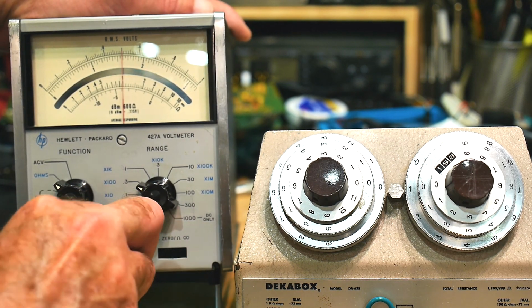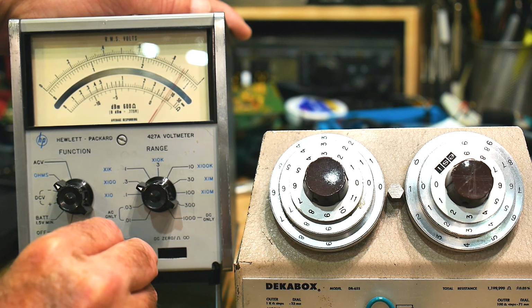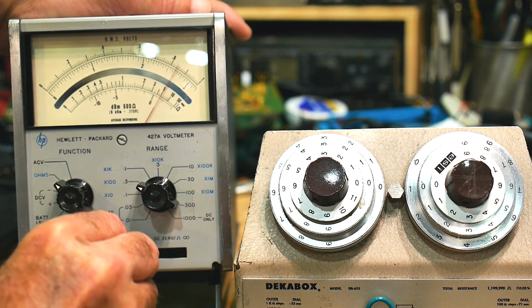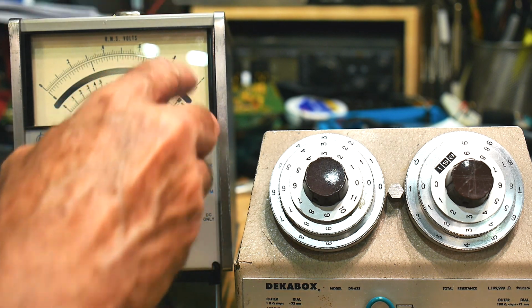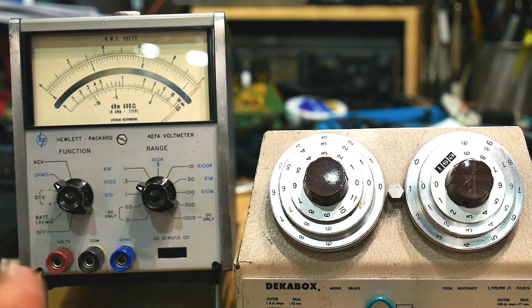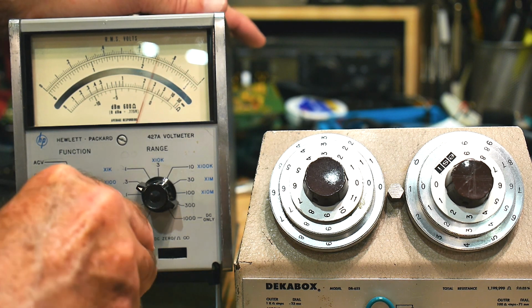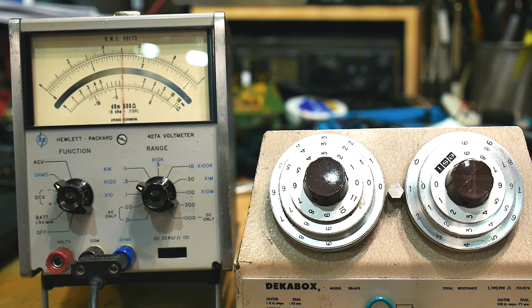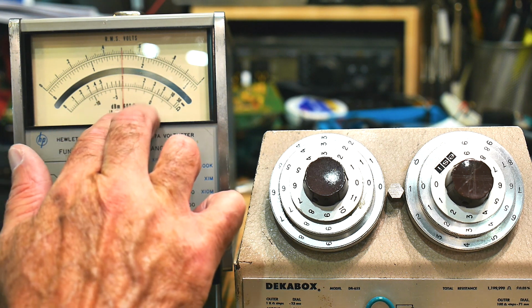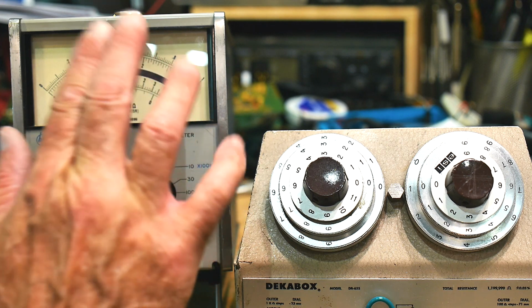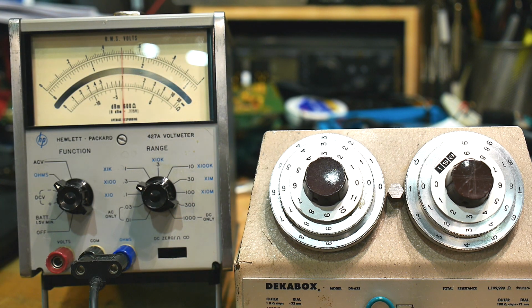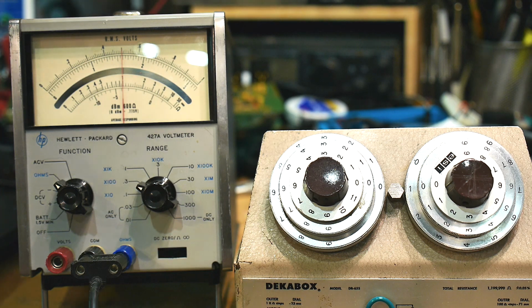I don't know if I can simulate that here, but if it was doing something like this, you'd say, oh, it's sort of 0.8, that kind of thing. Whereas on a digital meter, the numbers are flickering around and you just can't read them. So it's great for audio type things. This one is especially good for audio because it'll give you dBm into 600 ohms. dBm is calibrated so that 0 dBm is 0.775 volts at 600 ohms impedance. And if you want to use a different impedance, there is a correction chart in the manual.